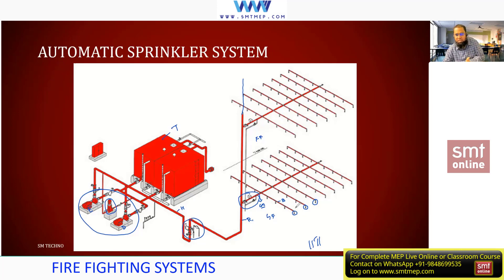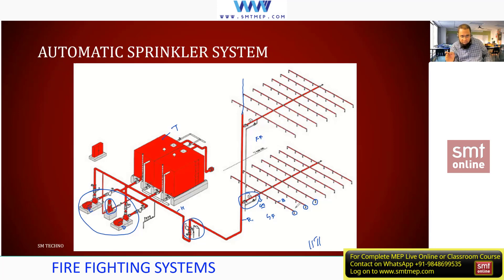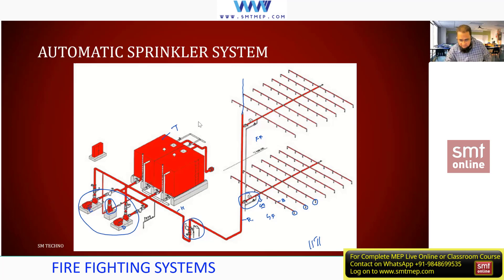The pumps suck water from the tank and supply it to the affected area. What I just explained is the wet sprinkler system — the pipes are always loaded with water, which is why it's called the wet sprinkler system. In western countries, the dry sprinkler system is common; we also have pre-action and deluge systems, which will be discussed in the NFPA module. In India or the Gulf, we generally use the wet sprinkler system.